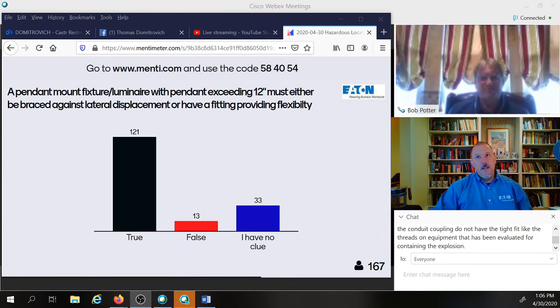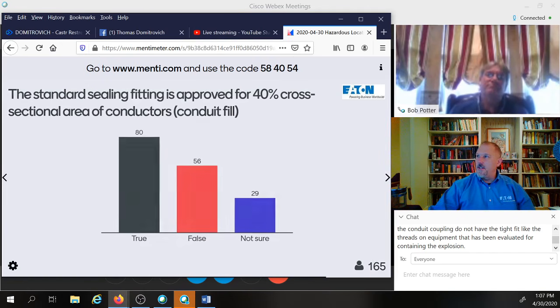And that is true. The permanent effective brace, as the code likes to say, needs to come down and connect on the pendant stem within 12 inches of where that stem connects to the luminaire. In the case of the flexibility, it needs to be within 12 inches of where that pendant stem connects to the junction box. Awesome. All right. So we have 123. That was consensus by majority too. So that was good.